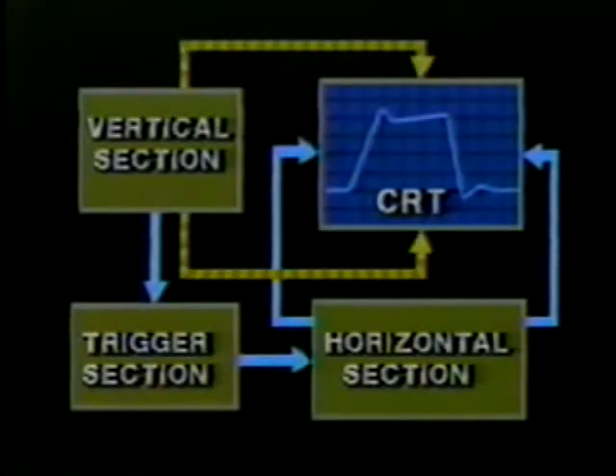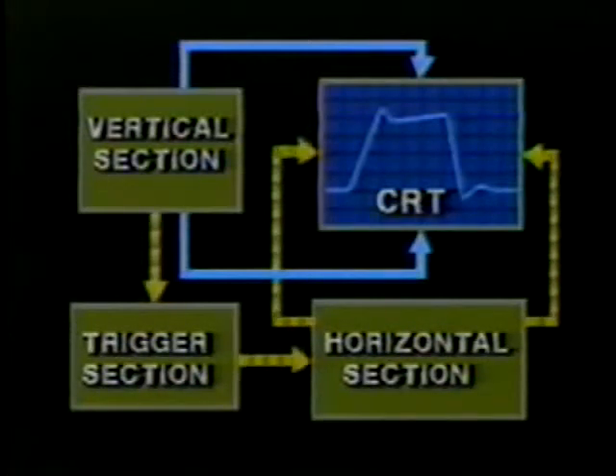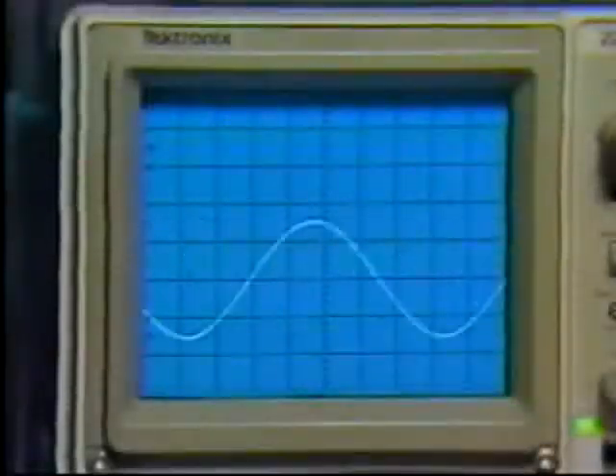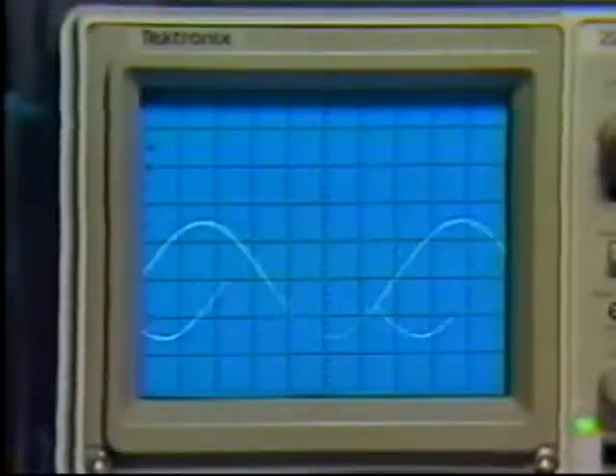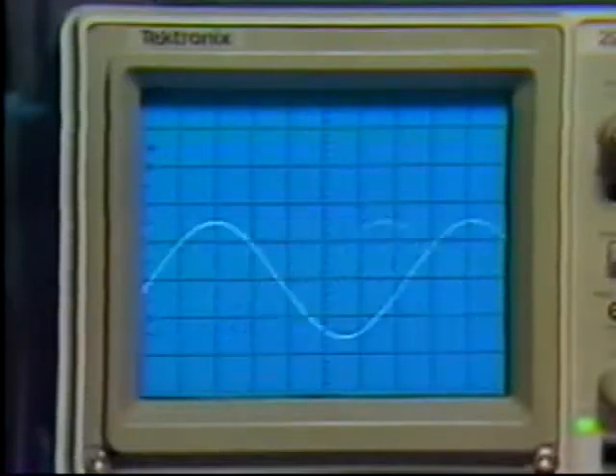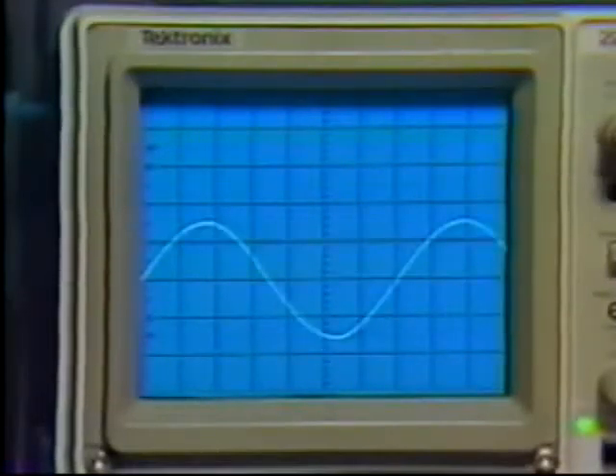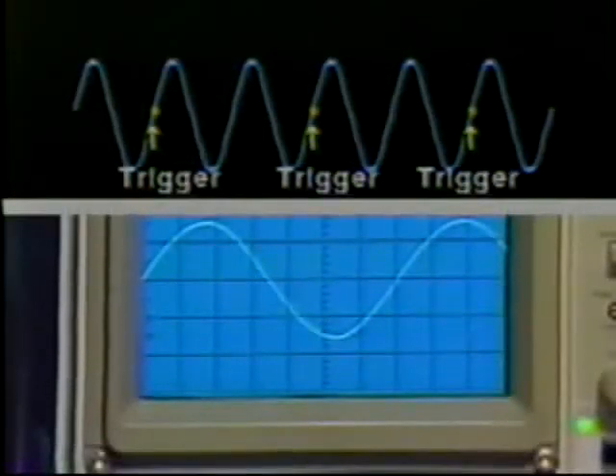We've examined the signal path through the vertical section; now let's follow the signal path through the horizontal section. The input signal is coupled from the vertical input BNC to the trigger circuit. The trigger circuit takes a sample of the incoming signal and shapes it. This shaped trigger signal starts the sweep, ensuring horizontal stability of the trace by beginning each sweep at the same point in relationship to the incoming signal. Without triggering, the trace would free run — each sweep would start at a different time, resulting in a confused collection of unmeasurable traces.